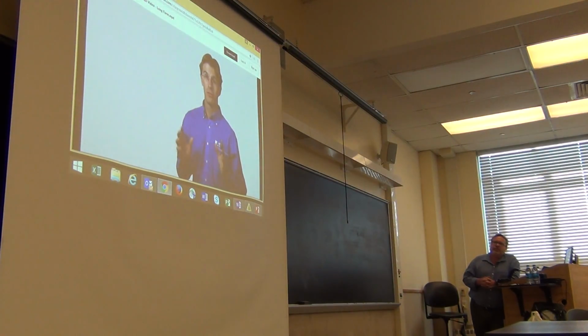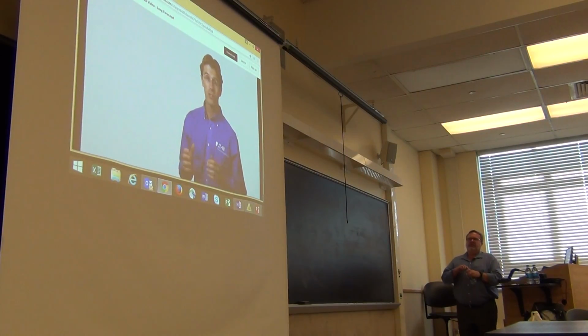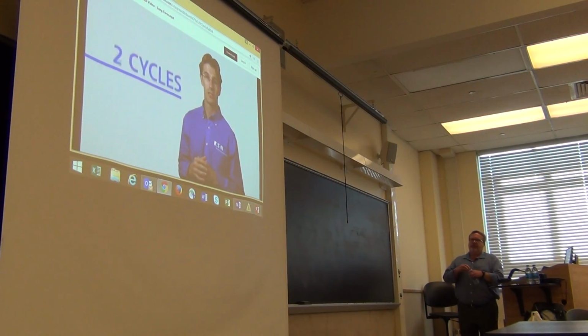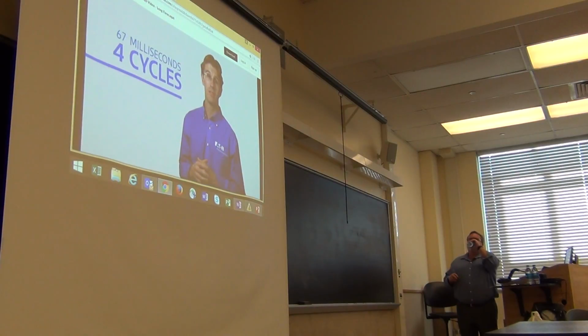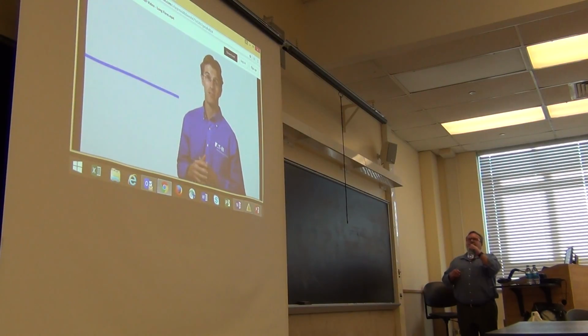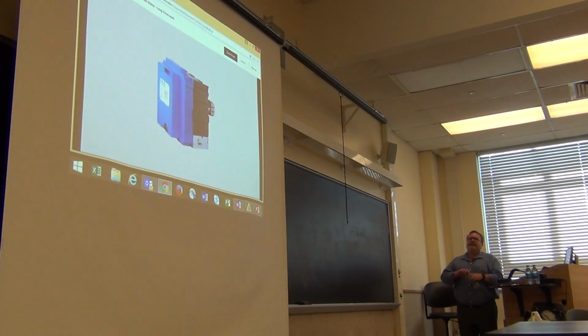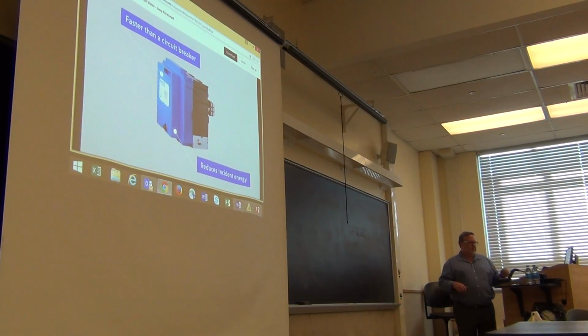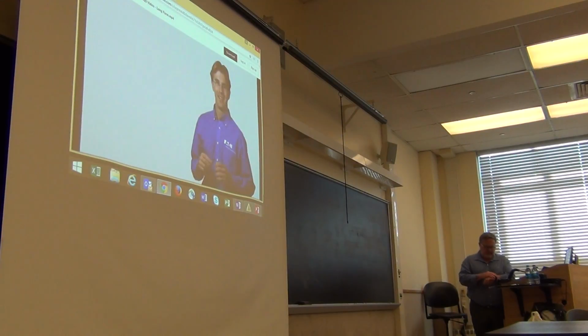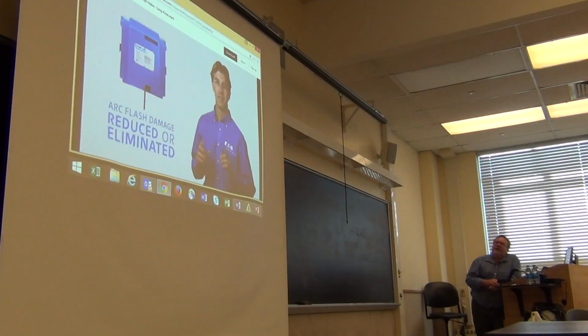Most methods for reducing arc energy rely on tripping the main circuit breaker to clear the fault. Unfortunately, low voltage power circuit breakers can take up to 4 cycles or 67 milliseconds to open. This is simply not fast enough. The ideal solution is a system that operates faster than the circuit breaker to reduce the incident energy even further. In fact, our team set out to develop a solution that reacts so quickly that the damage from an arc flash event is dramatically reduced or completely eliminated, not to mention what that would do for personnel safety.